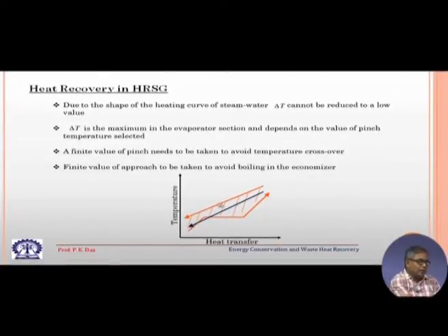So, to avoid this, we intentionally keep some sort of a finite pinch between the gas stream and the vapor stream, and that is why there will be a good amount of irreversibility, and a certain amount of waste heat recovery will not be possible.